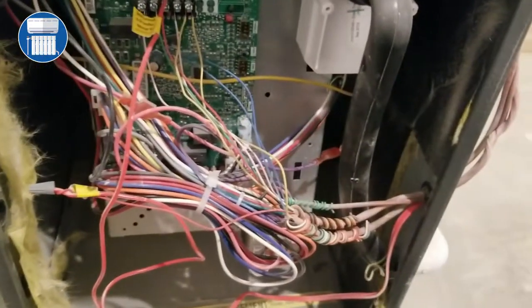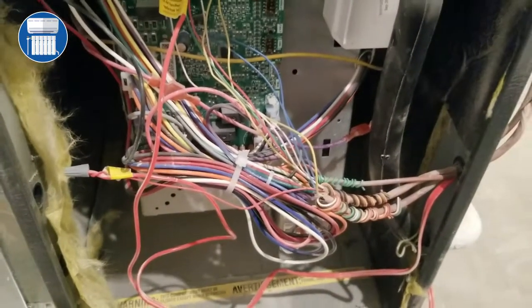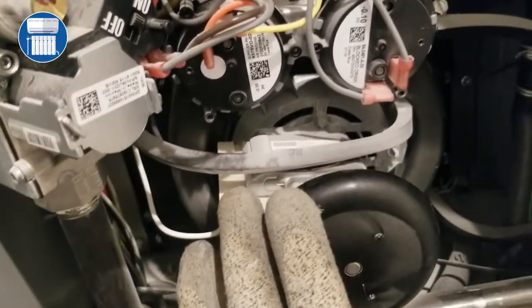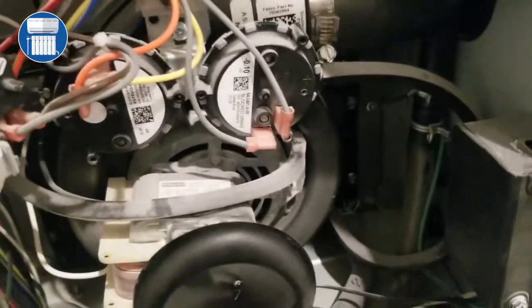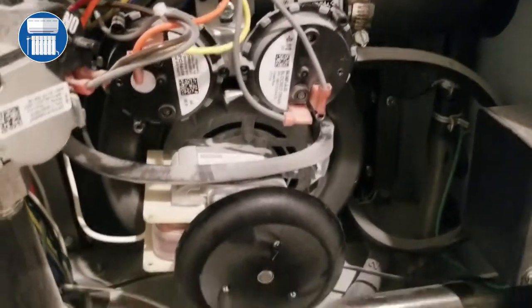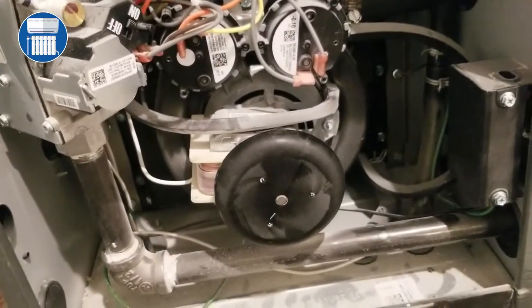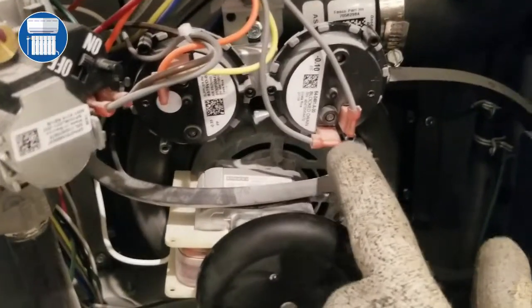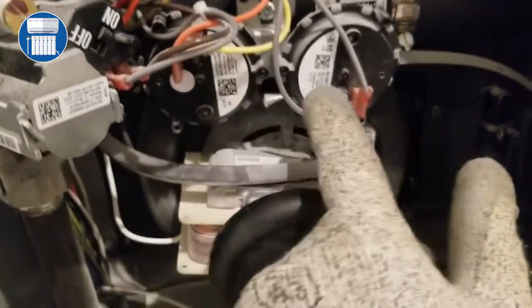We have 3 flashes. Now to fix this issue, most of the problem you're going to have with that pressure switch is these lines could get clogged. So you're going to pull this line out, pull this line out, and blow into these lines and make sure they're clear. Normally, if there's any water or anything in the line, it will cause your pressure switch to act up. If that doesn't work, take one of these lines out and blow in it gently to move the diaphragm of that pressure switch. And if those 2 things don't work, your next step may be to change the pressure switch, or you could check the voltage, which I have another video on how to check a pressure switch properly. You may want to check that video out.